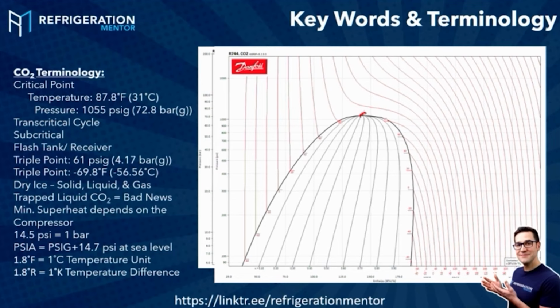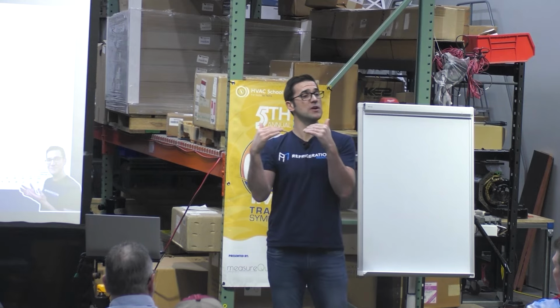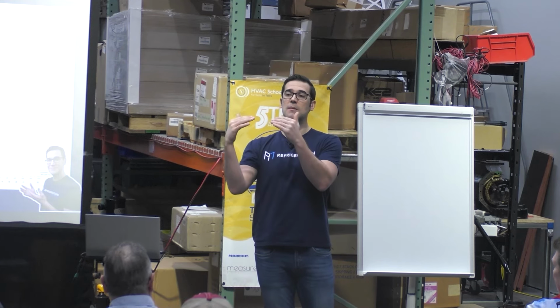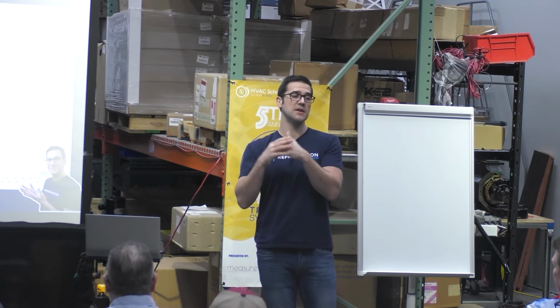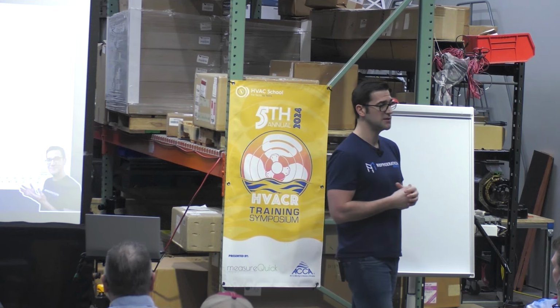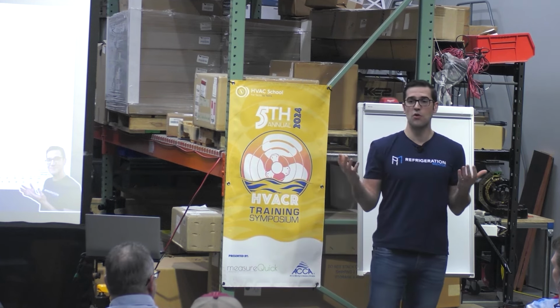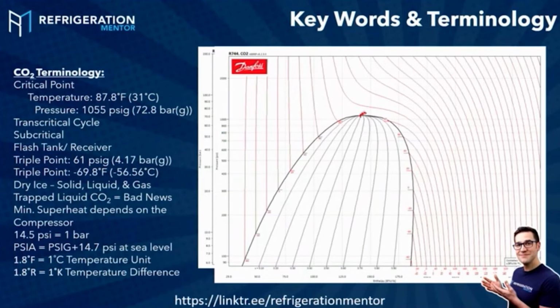Nailed it, Chris. Love it. 87.8. So when we get above that temperature outside, that means we are above the critical point, and now we're in something called a transcritical or supercritical state. So there's just no pressure-temperature relationship. That's really what you want to understand. And this is kind of what it looks like versus the other one. So if I draw this like this, we go up like this, we're above the critical point, we come down. And this is the transcritical state.